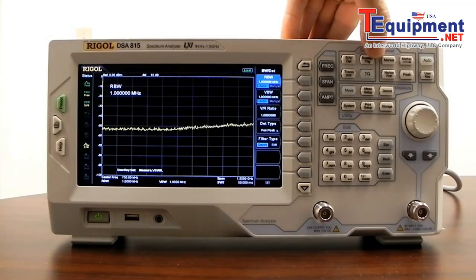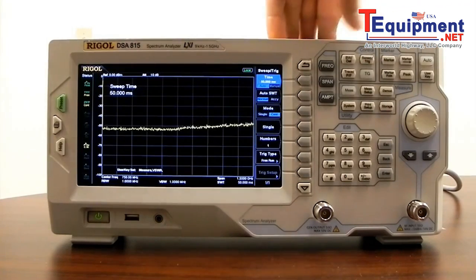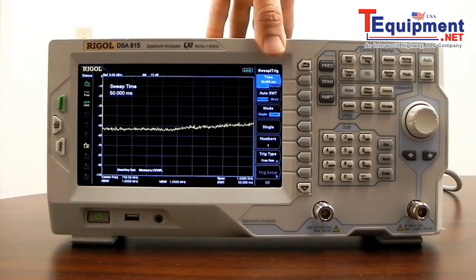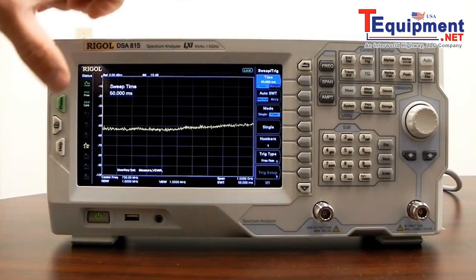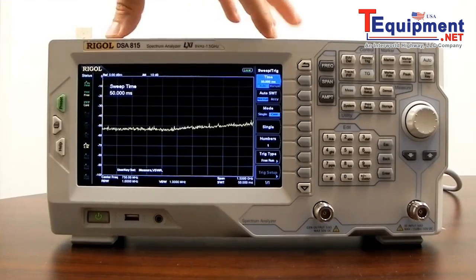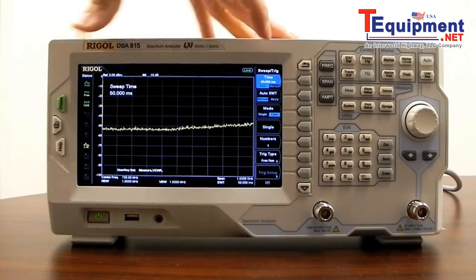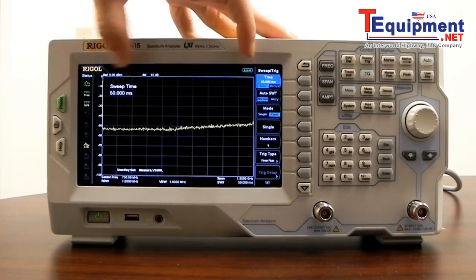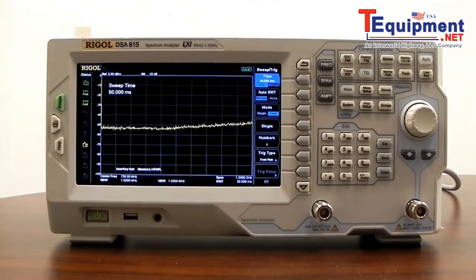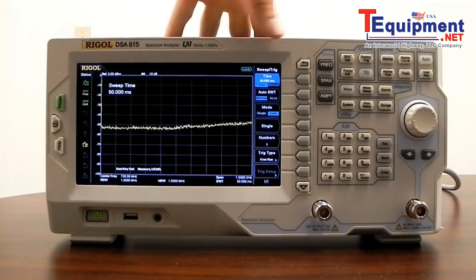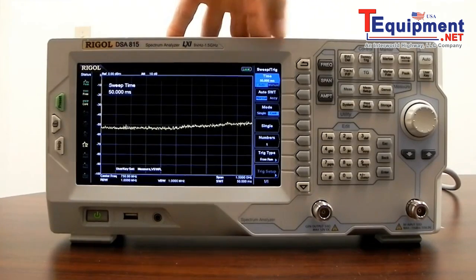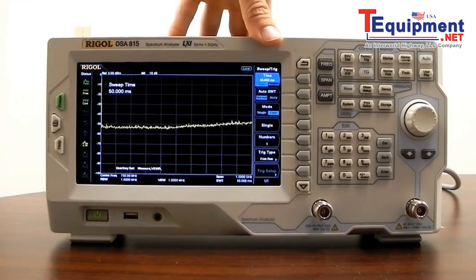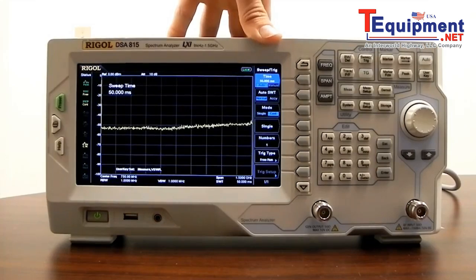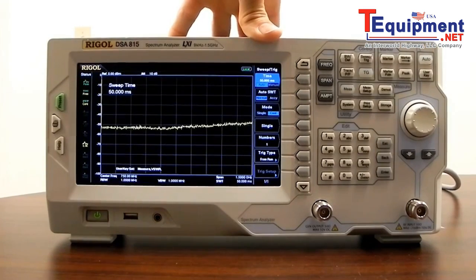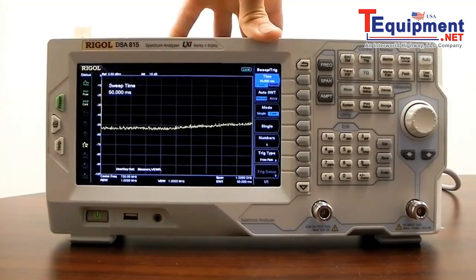And now let's take a look at the sweep and trigger. We can set the sweep time. Typically that sweep time is going to be on auto, based on the amplitude and the sweep configuration that we have set. The frequency range, the span, and the resolution bandwidth determine that sweep time if we're in auto mode, and that's going to be calibrated. If we go to a manual mode, it's going to be uncalibrated because we're forcing the box to do things that it's not necessarily optimized to do in a calibrated sense.